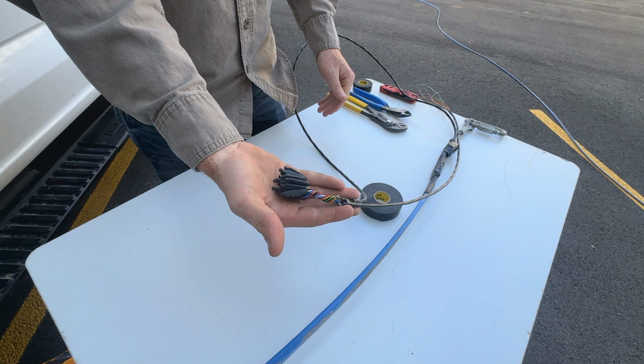To begin, you are going to need to find the nearest splice point to the temperature cable. If your cables are hung inside chimney ports, a likely location for this splice would be in the chimney port. If your cables are hung from an eye bolt, a likely location for this splice would be a stub-up or a conduit. These splices should be taped up to keep them out of the elements. You may need a knife to help remove the tape.